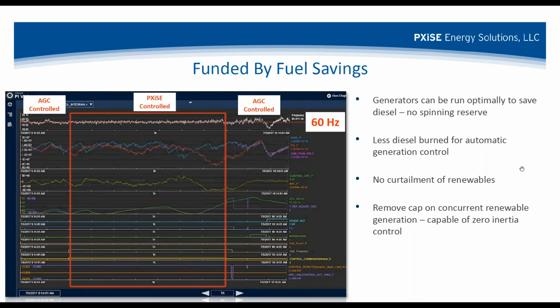We did have communication with grid operations and asked them at times, based on PXiSE recommendations, to have the thermal generation go up or down a little bit based on what was going on with renewables. But that was a slow process, just to make sure there was enough energy, or not too much, on the grid for what the batteries can handle. All the energy being generated was accepted onto the grid, and PXiSE was able to control it - you can see within the red box, when PXiSE had control, that top graph, how tight the frequency was.